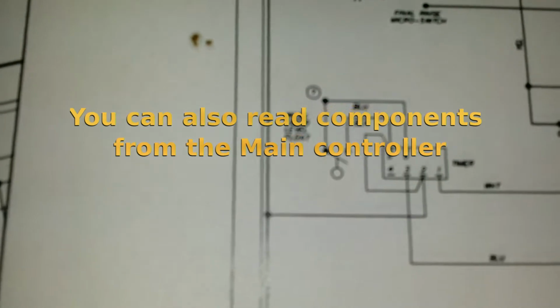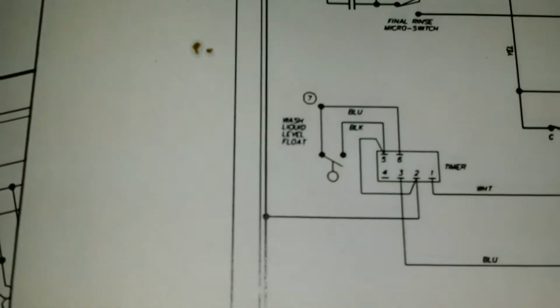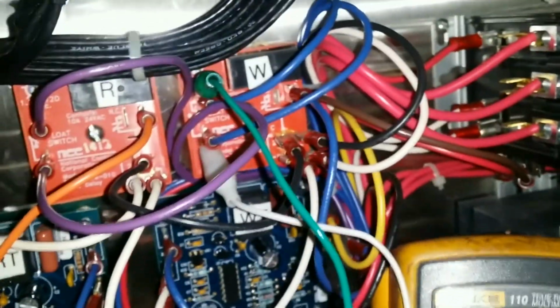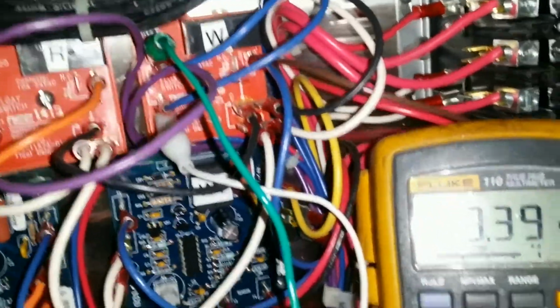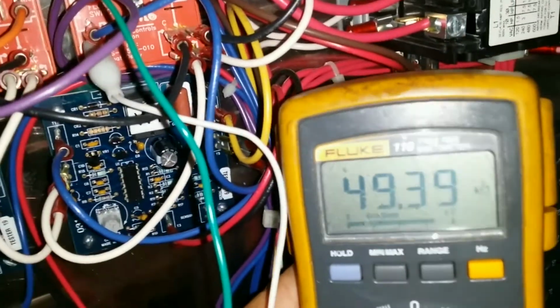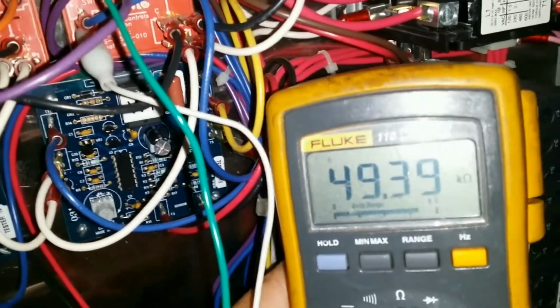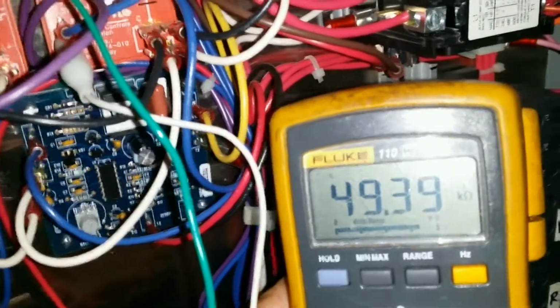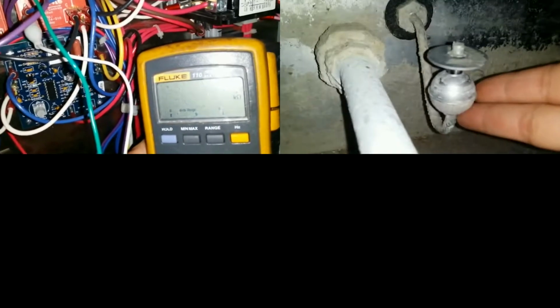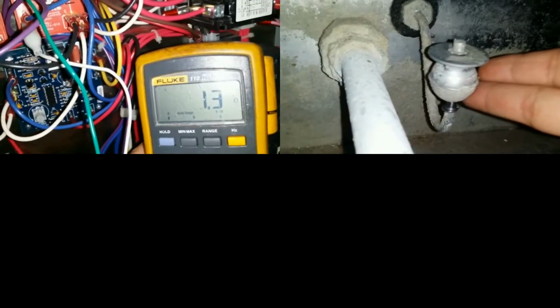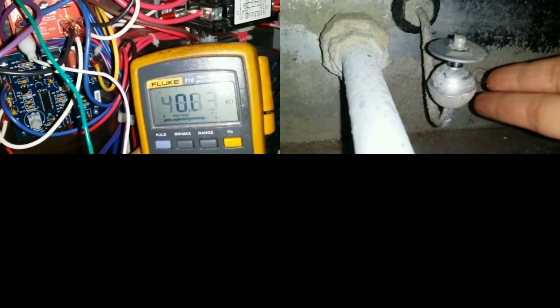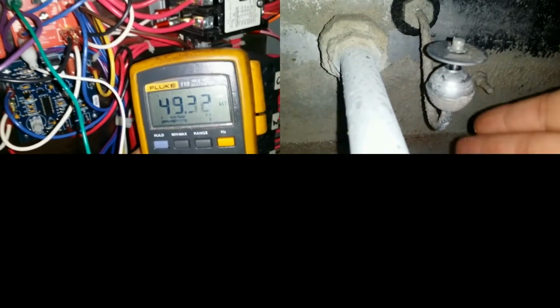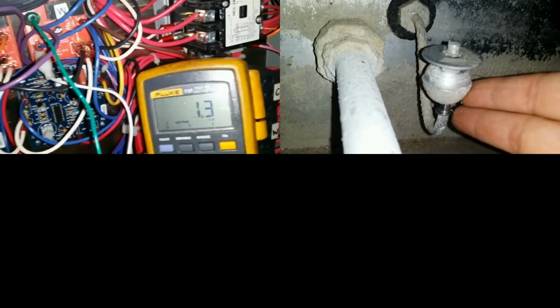I want to read my flow switch, and since it's connected to the circuit card, that's what I'm gonna do, read it from the circuit card. I'm connected to the circuit card, and I got the flow switch, a multimeter connected to it. Go ahead and close the flow switch, simulate that it's full of water. Now simulate that it's empty. And full of water, please. There, we tested our flow switch.